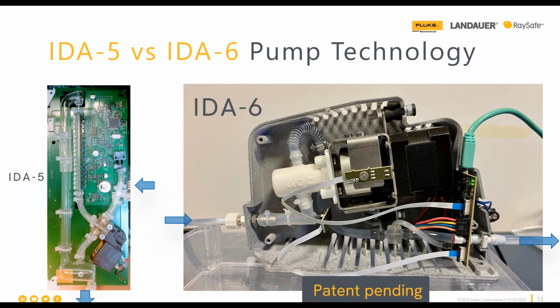On the left is the internal workings of one of our IDA-5s. If you're familiar with the IDA-5, IDA-4 is something very similar. I mentioned that glass chamber. You can see it there on the far left by the word IDA-5. That's that glass tube. What would happen is this would fill up with fluid, and then once it passed those photo eyes, each of those photo eyes were a set designation. But the problem is over time, that glass tube could get cloudy, or if you accidentally used mineral water. So there's lots of issues there.